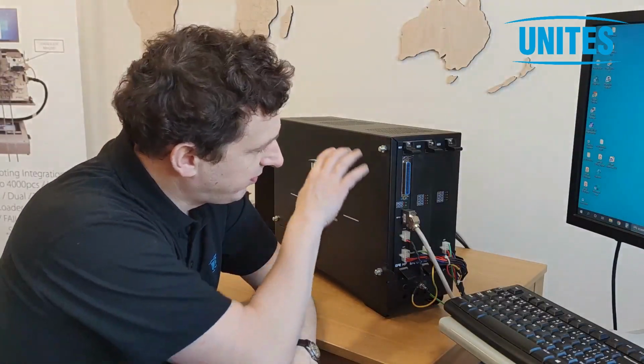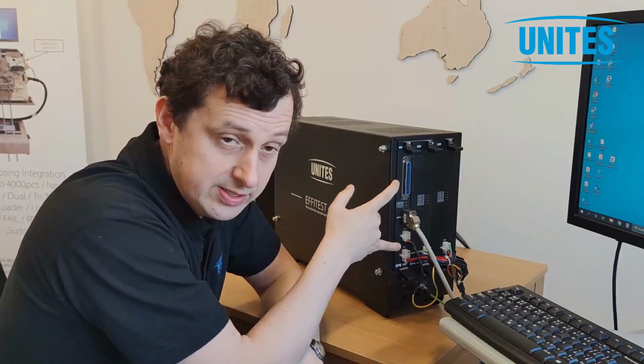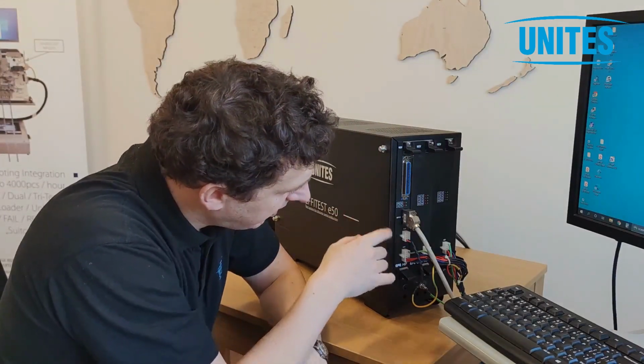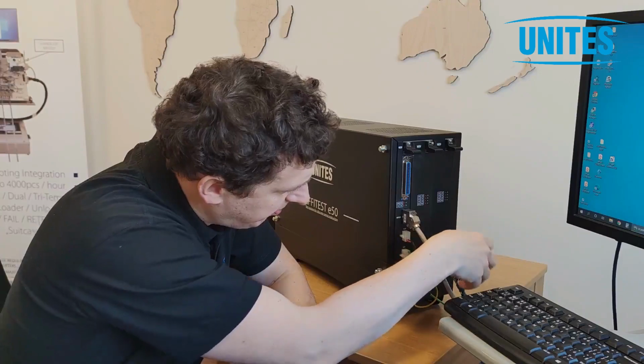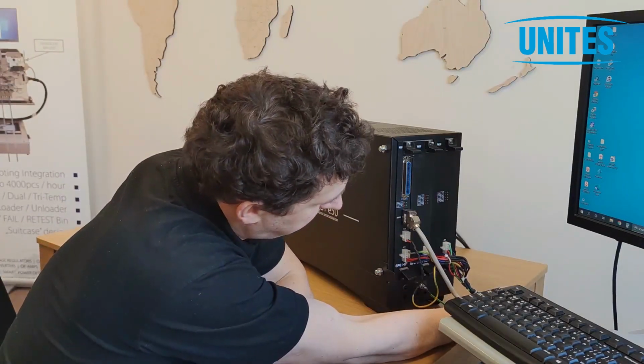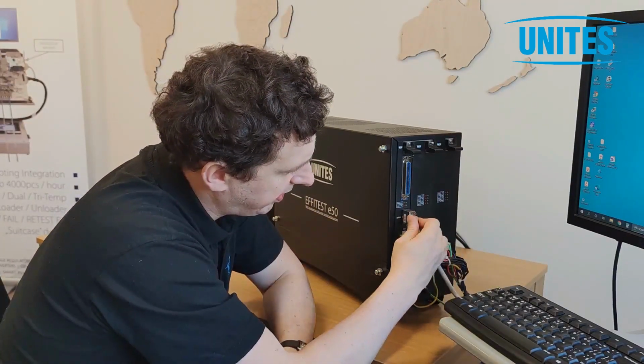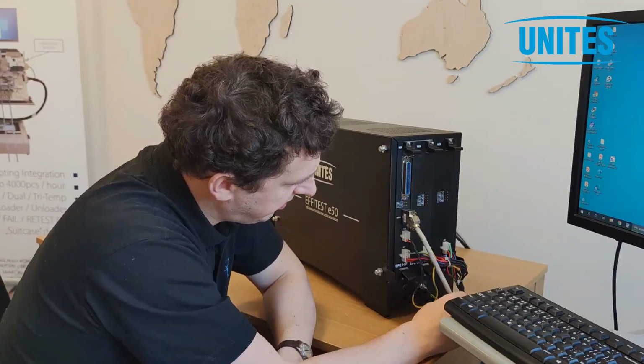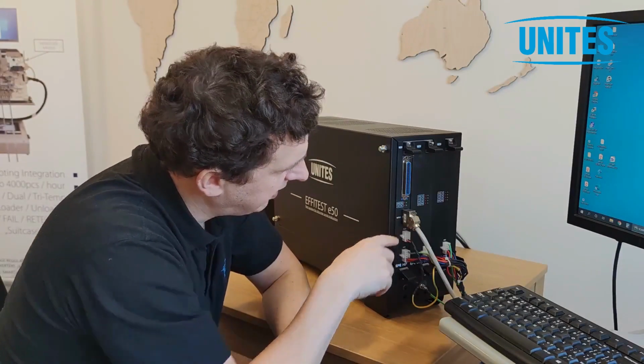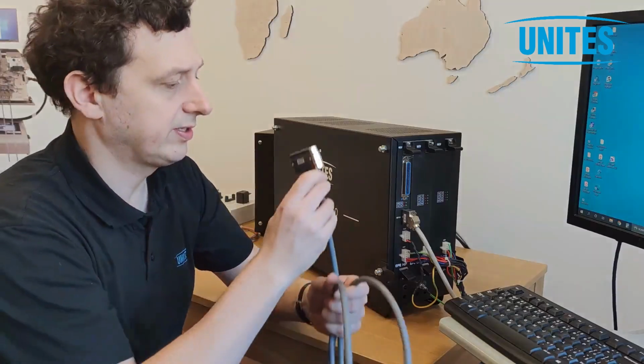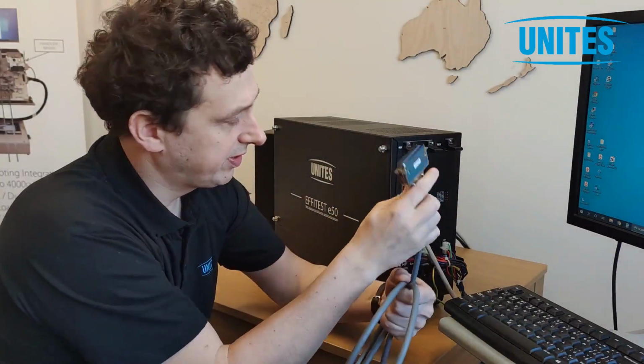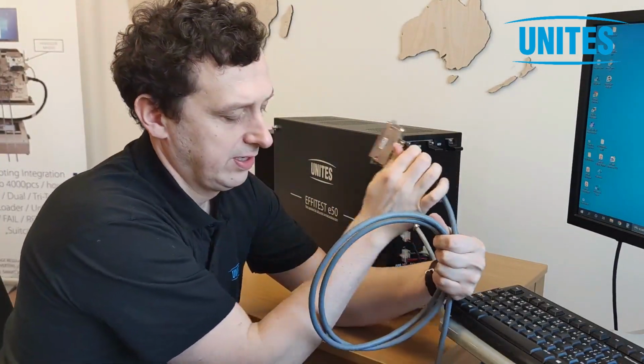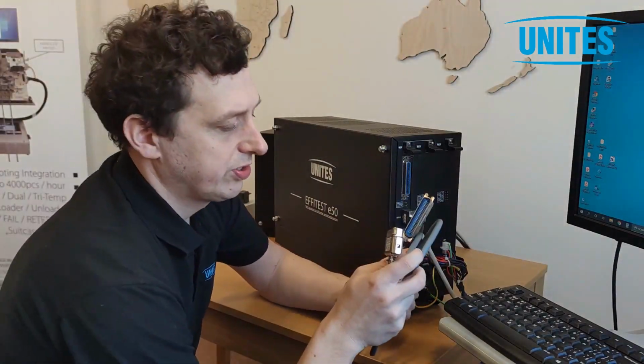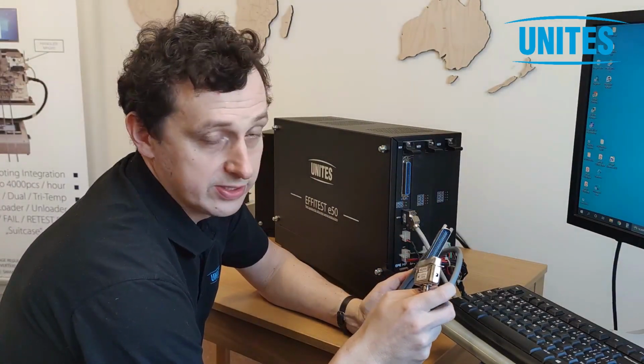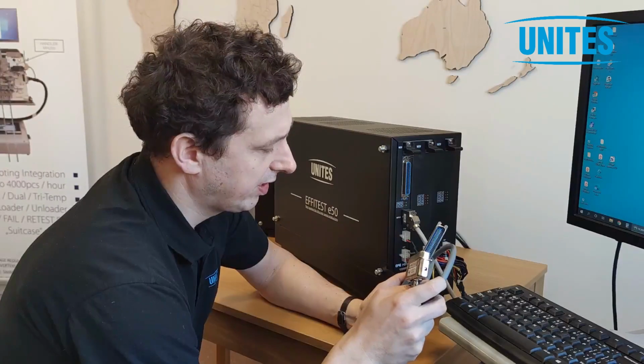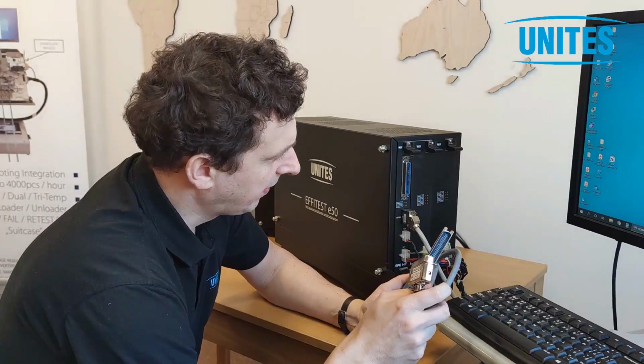On the back side of the test head there is a handler interface which is powered by this connector, which goes to the power box. Communication with the PC is via this signal cable, and to the handler it's connected by a Centronics 50 cable, which could be further adjusted if necessary, if there is a different type of handler, not a standard one.